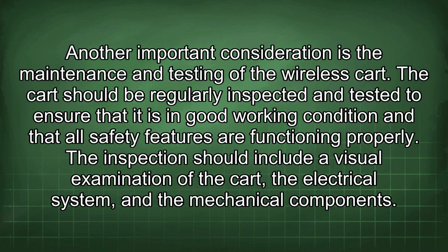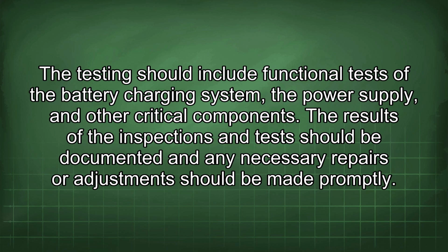Another important consideration is the maintenance and testing of the wireless cart. The cart should be regularly inspected and tested to ensure that it is in good working condition and that all safety features are functioning properly. The inspection should include a visual examination of the cart, the electrical system, and the mechanical components. The testing should include functional tests of the battery charging system, the power supply, and other critical components. The results of the inspections and tests should be documented, and any necessary repairs or adjustments should be made promptly.